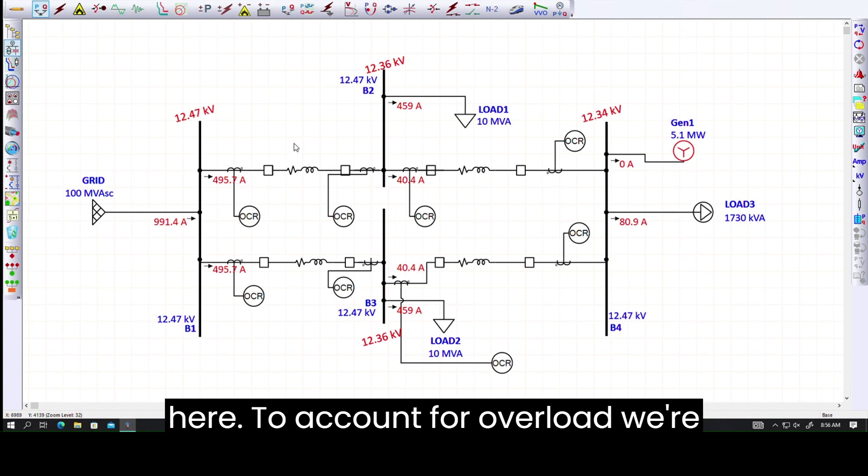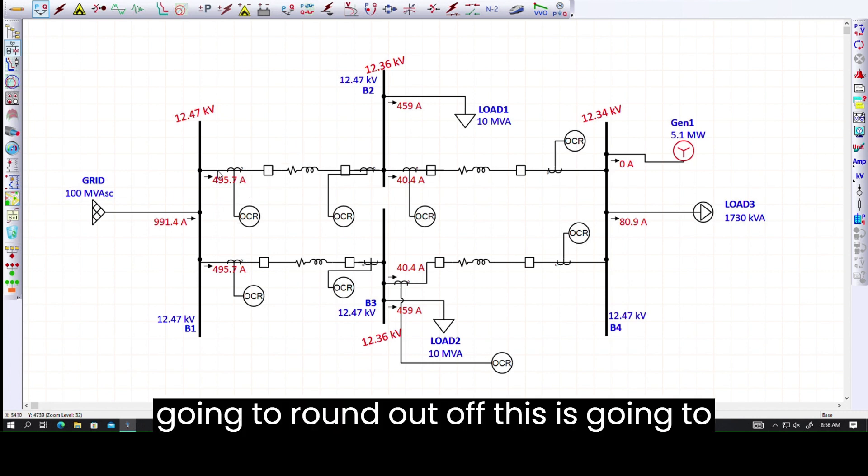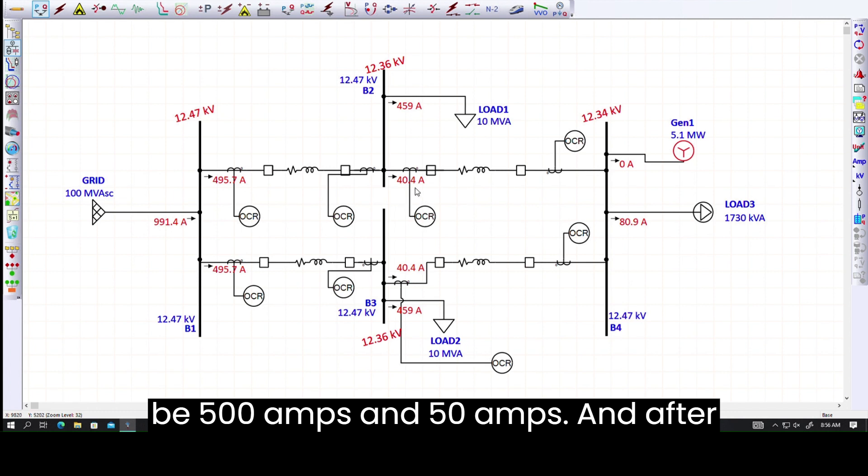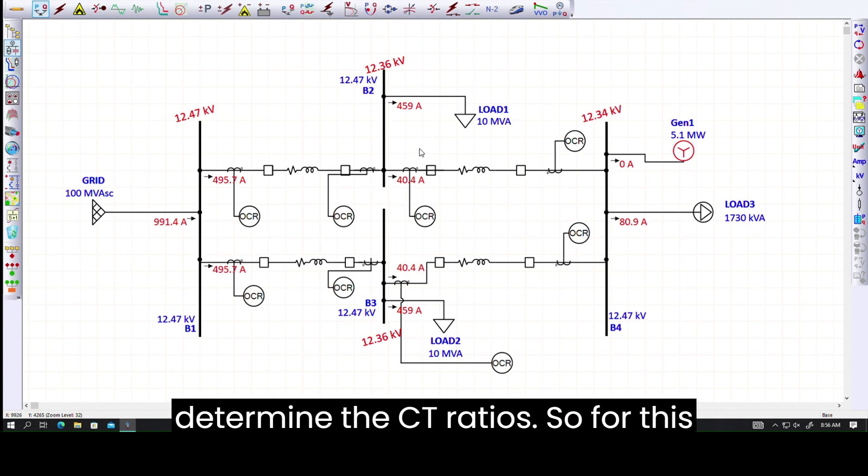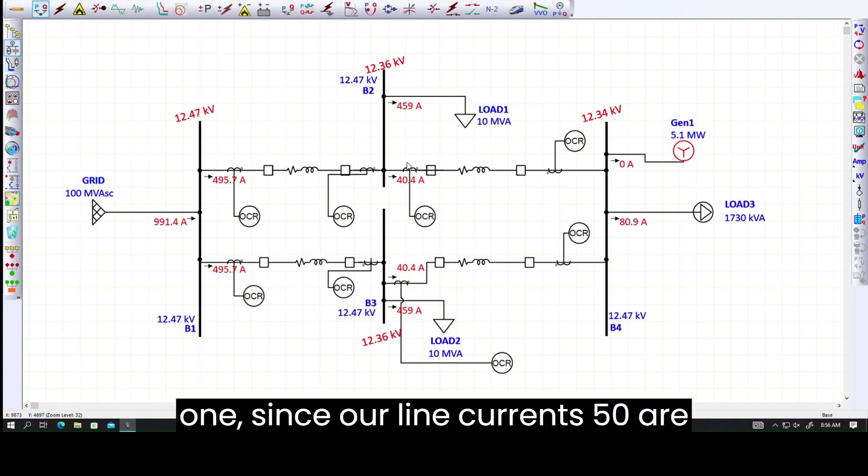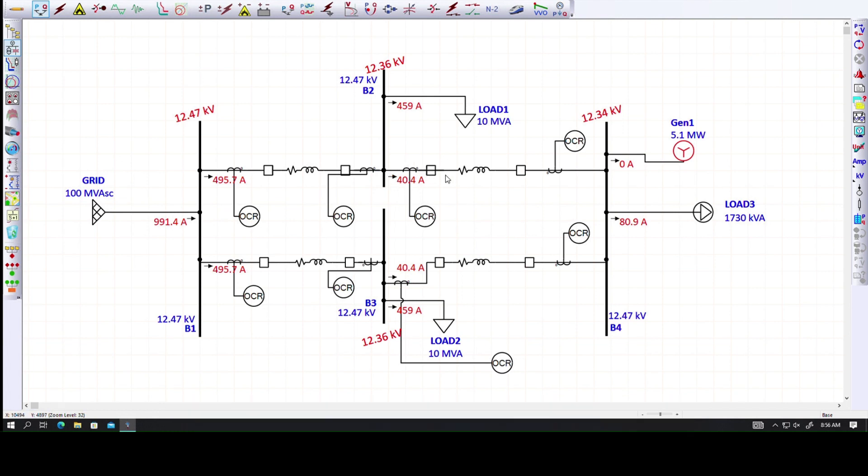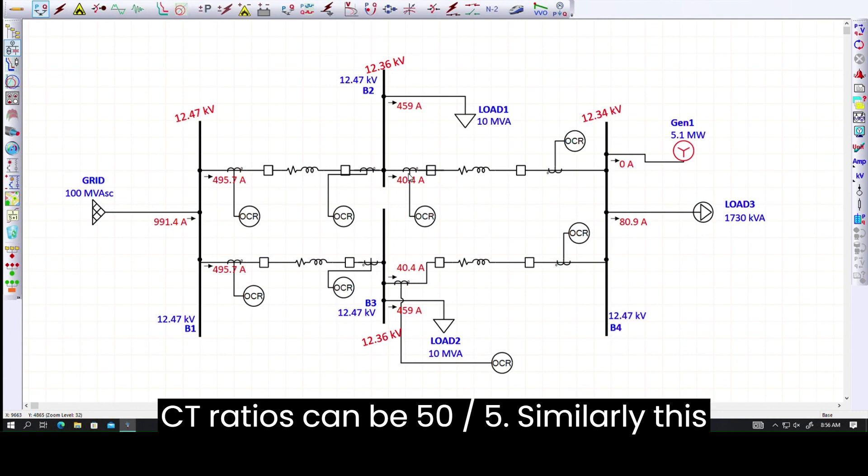To account for overload, we're going to round that off. This is going to be 500 amps and 50 amps. After determining our line currents, we can determine the CT ratios. For this one, since our line current is 50, our CT ratio can be 50 over 5.